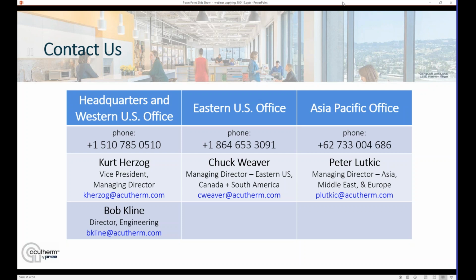And I do have a couple questions that I want to touch on before we run out of time here. So I'm being asked where Therma-Fuser diffusers are applicable and where not applicable. Well, they are a VAV diffuser, and they'll work typically anywhere a VAV system will work. So something like a hospital in the U.S. where there are requirements for pressurization and air changes per hour, typically not a typical VAV application and not a good application for a Therma-Fuser diffuser. But a medical office building, great application. Those buildings have lots of small offices, exam rooms, and being able to provide those small zones of control that the Therma-Fuser can provide is a great way to design those buildings.